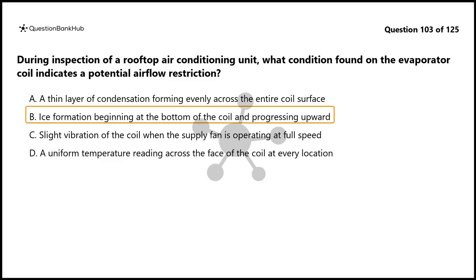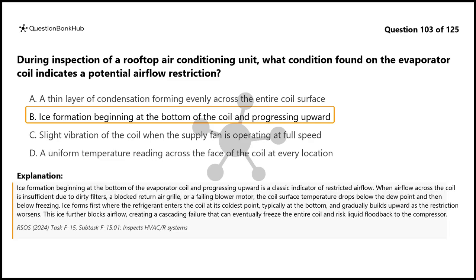The correct answer is B. Ice formation beginning at the bottom of the evaporator coil and progressing upward is a classic indicator of restricted airflow. When airflow across the coil is insufficient due to dirty filters, a blocked return air grill, or a failing blower motor, the coil surface temperature drops below the dew point and then below freezing. Ice forms first where the refrigerant enters the coil at its coldest point, typically at the bottom, and gradually builds upward as the restriction worsens. This ice further blocks airflow, creating a cascading failure that can eventually freeze the entire coil and risk liquid flood back to the compressor.